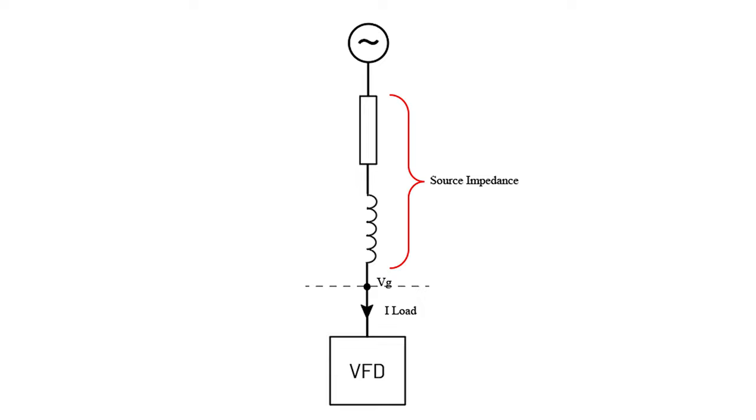Now we can replace the transformer with a Thevenin equivalent — a simple electrical model that will explain how the harmonics are actually affecting the voltage. Consider the second picture: we have an ideal voltage source on the top, an inductor, and a resistance. These two components model the source impedance of the grid, and the load will pull current through those impedances.